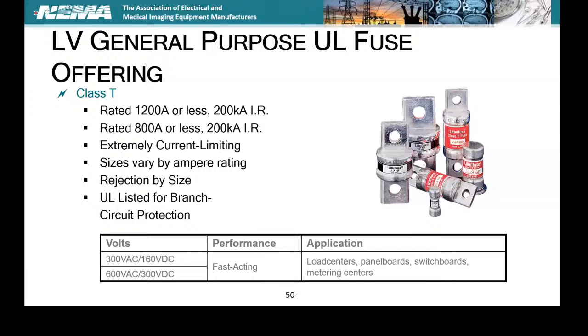But your Class T is for tiny, L is for large. Up to 1,200 amps though. They pack a punch: 200,000 amps of interrupting rating. Extremely current limiting. So you can imagine what that curve looks like. It's a steep slope. Where it crosses 0.01 seconds is not too far away from the long time region for the amp rating of that fuse. So it's a steep sloped fuse.